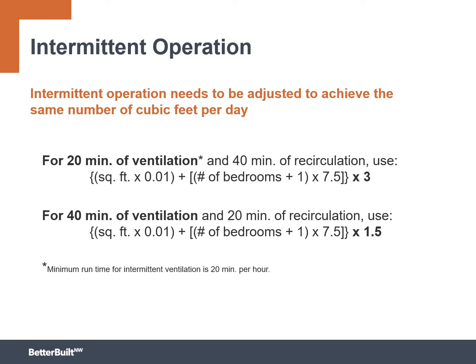What if you decided to run it 40 minutes out of every hour? You still need to multiply it by 1.5. Now, that is, again, a big change. So we really are thinking with heat recovery and energy recovery ventilators, whether they're spot, standalone, or integrated, running them continuously is the best way to ensure that you can have a flexible number of HRVs to choose from, which can help you reduce cost, make it easier to install, and maybe even cut down noise when they're running, because a 55 CFM continuous heat recovery ventilator is likely to be a little bit more quiet than a 165 CFM unit that is running intermittently.